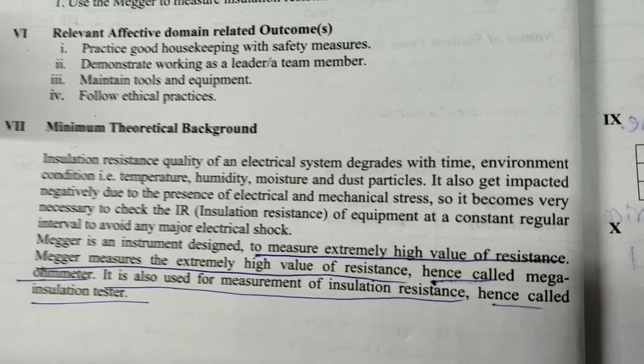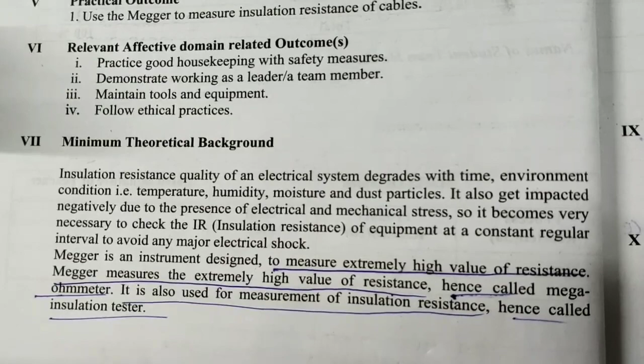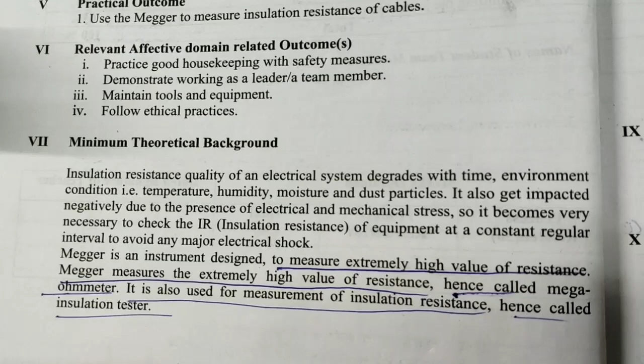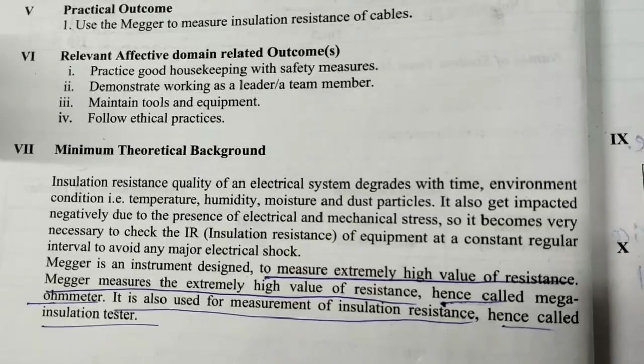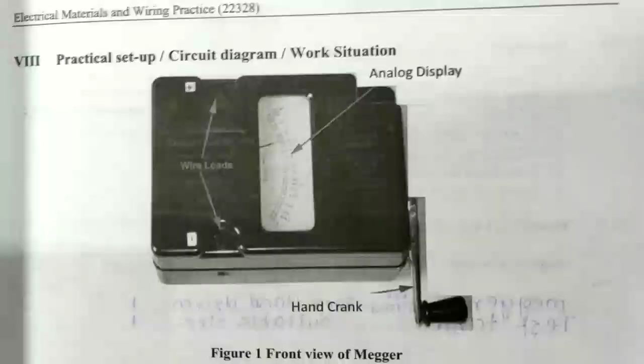Megger is an instrument designed to measure extremely high values of insulation resistance. Means Megger measures extremely high values of resistance, hence it is called a Megger or megohm meter. It is also used for measurement of insulation resistance, hence it is called an insulation tester.